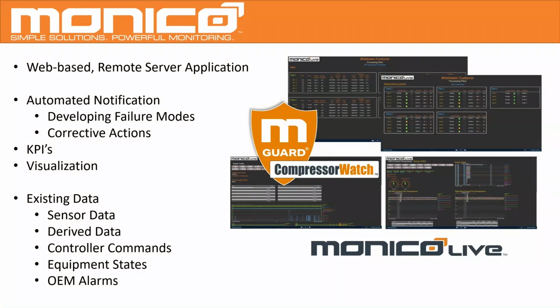It uses existing compressor package data to, 1, automatically notify operators of developing failure modes so that corrective action can be taken before an unplanned outage or serious damage occurs; 2, provide KPIs such as runtime, utilization, reliability, and mean time between outages; 3, provide visualization of real-time compressor package data. It is not necessary to install additional sensors or devices on the compressor package with CompressorWatch. However, the size of the dataset can impact how specific the recommendations are.